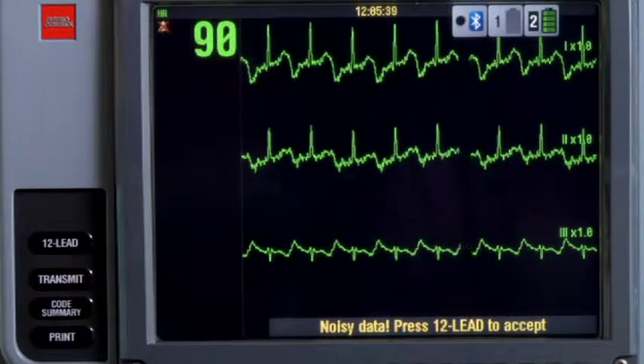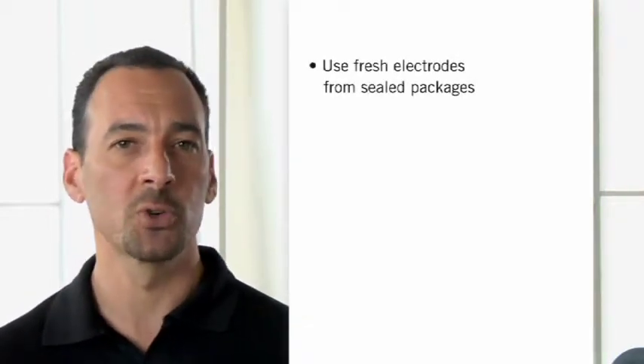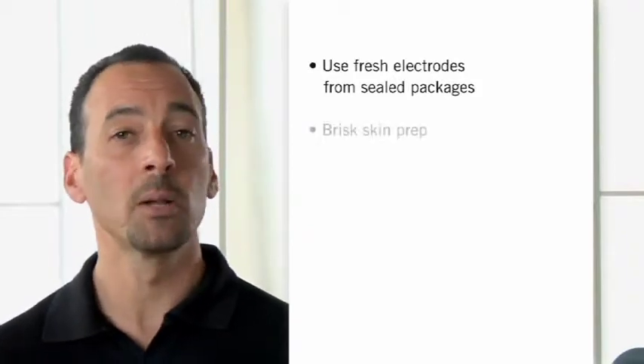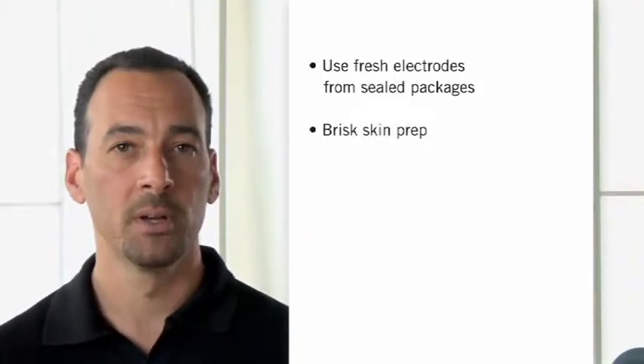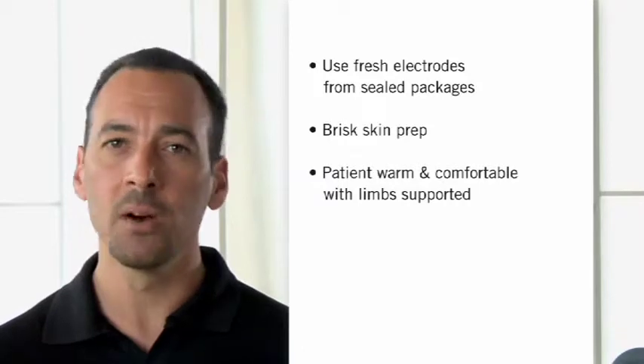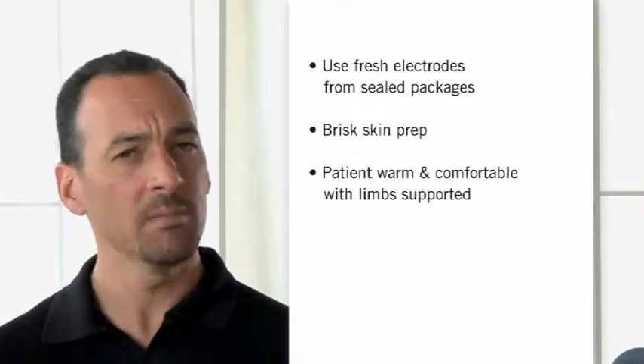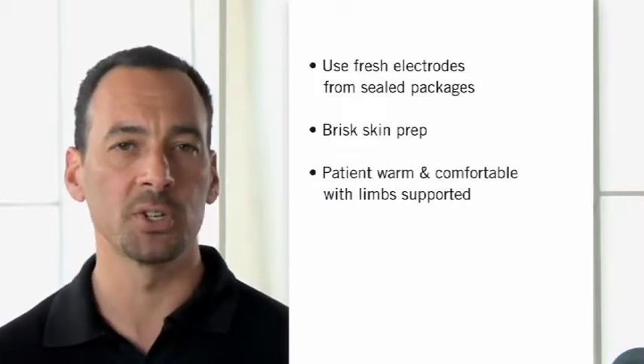The noise is usually patient or electrode related. So here are some preventive things you can do to avoid common sources of ECG noise in the first place. Use fresh electrodes from sealed packages. Develop the habit of a brisk skin prep. Make sure the patient is warm and comfortable with arms and legs supported. That goes a long way to reduce noise from muscle tension.